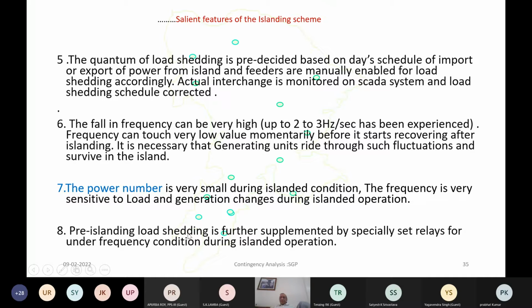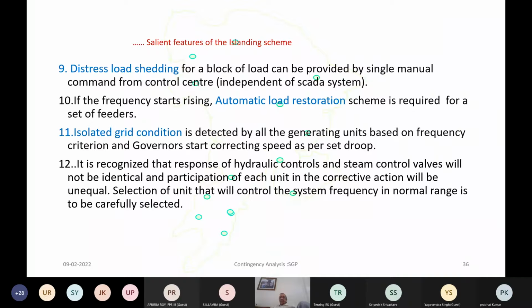It is also important that before the actual island takes place, that means before you open the tie lines, adequate load shedding should happen. If load keeps hanging on when you open the tie points, it's very likely that the island will collapse because there will be very heavy load and the frequency will sink. Then you require supplementary control schemes like a distress load shedding scheme. You require automatic load restoration schemes. That means after islanding, when the frequency starts rising, you should immediately put on certain load so that the island frequency gets stabilized. The supplementary controls will have to be designed in the governor to recognize the isolated grid condition.